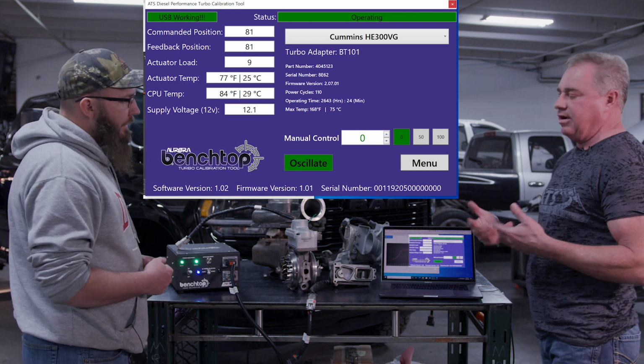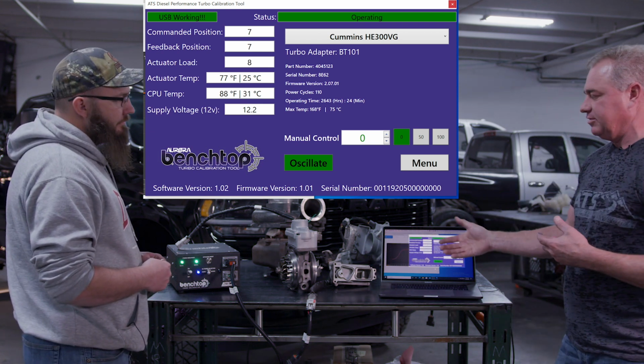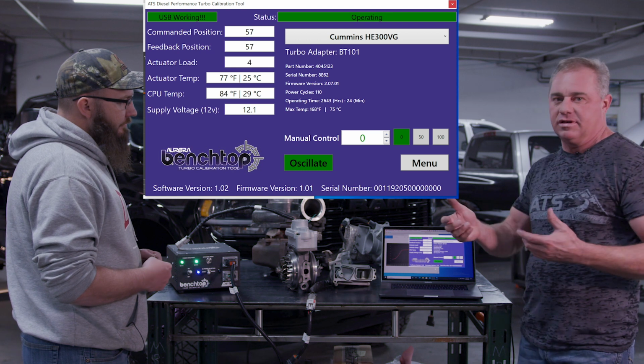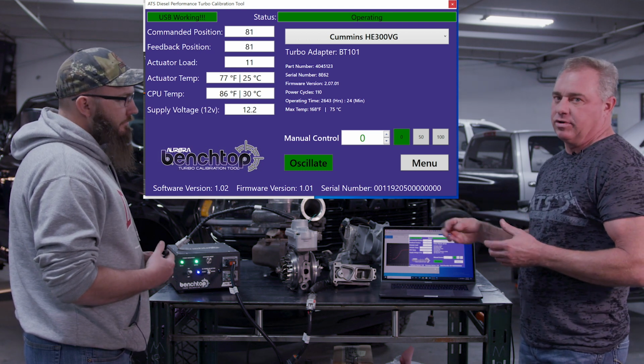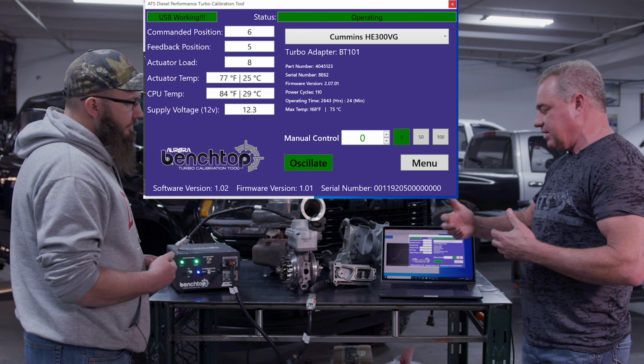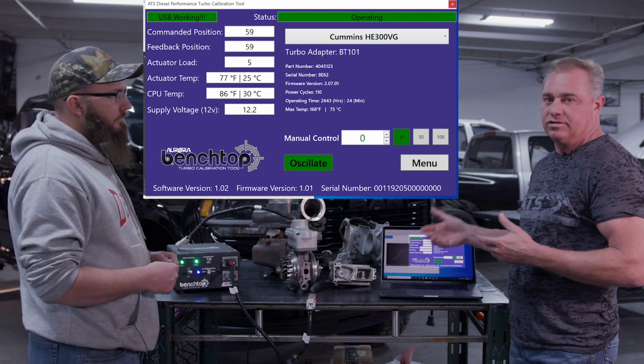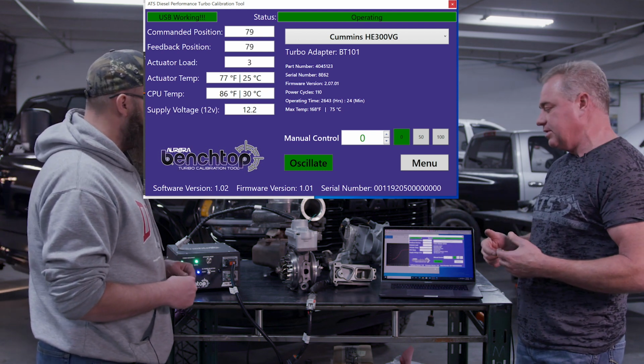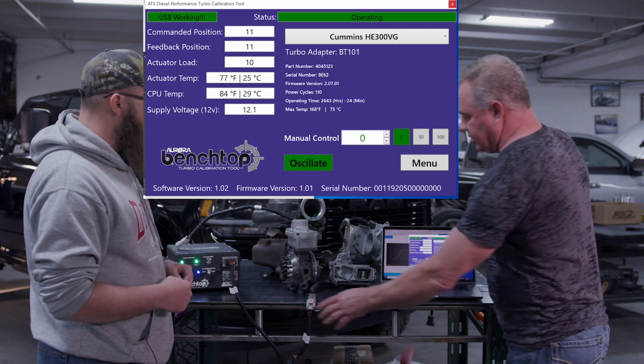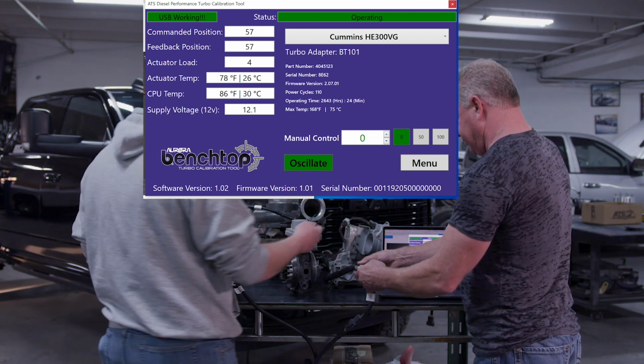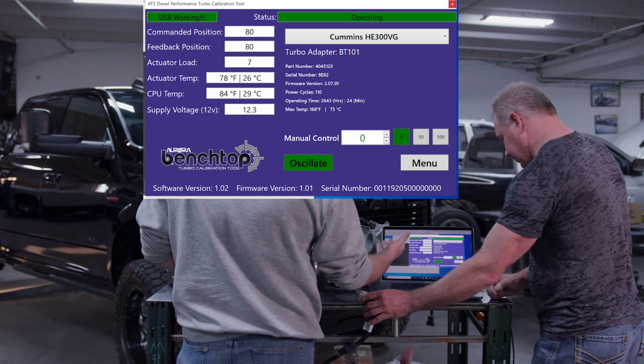But you'll really get comfortable with how to use this software and how to test the turbo - what's a perfectly good actuator, what's a failing actuator, one that's sticking. The software actually shows you that as well, as when it starts to sweep from 0 to 100%. So we'll dig into this real quick and do the calibration. I was going to point out to you right here that this actuator is obviously older.